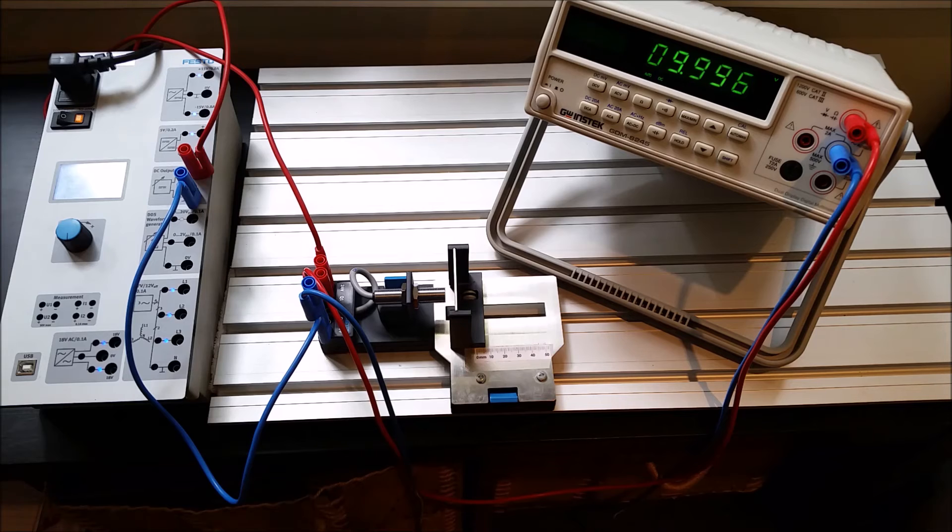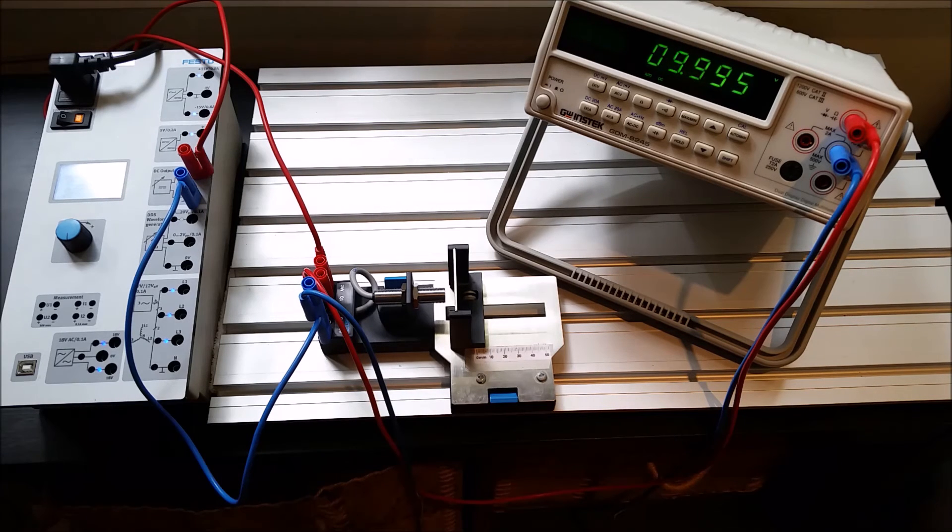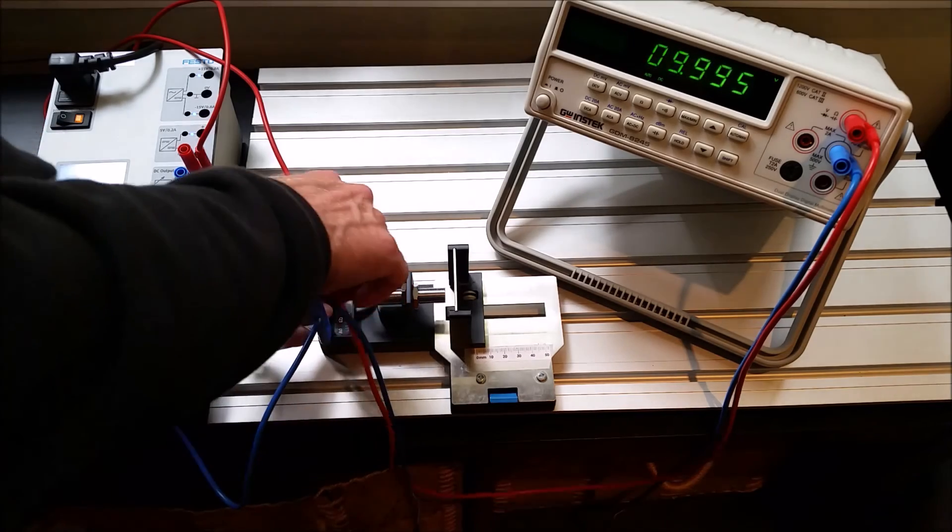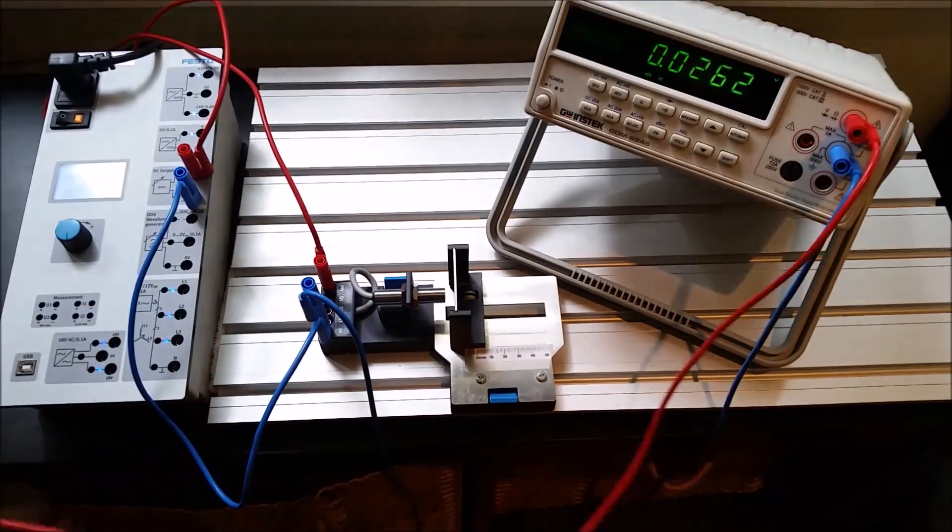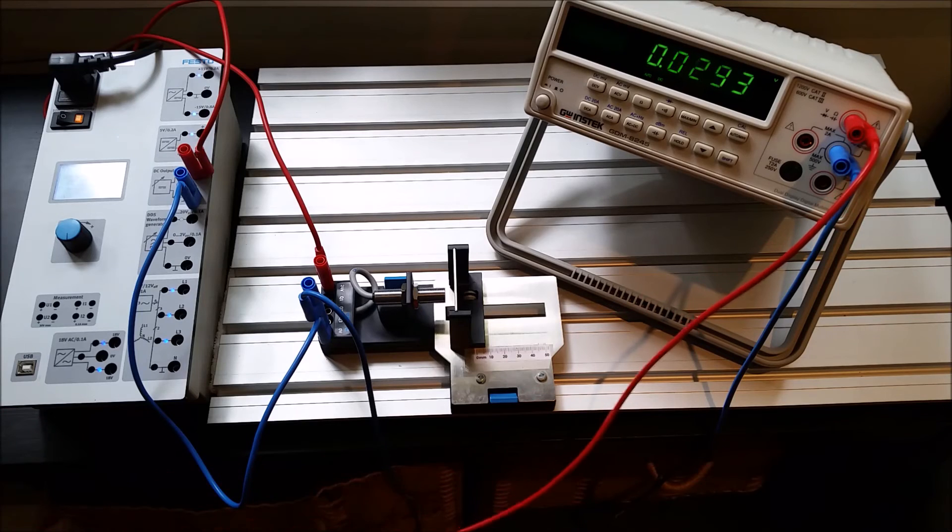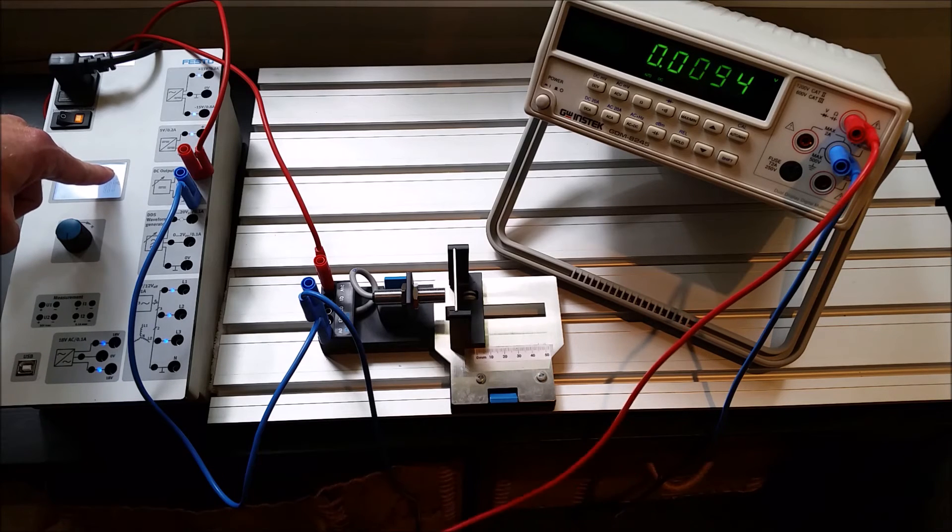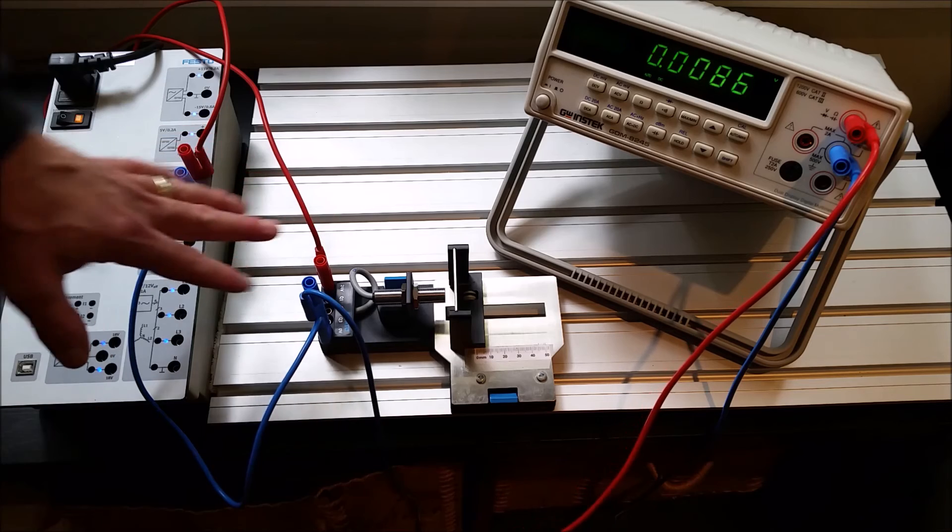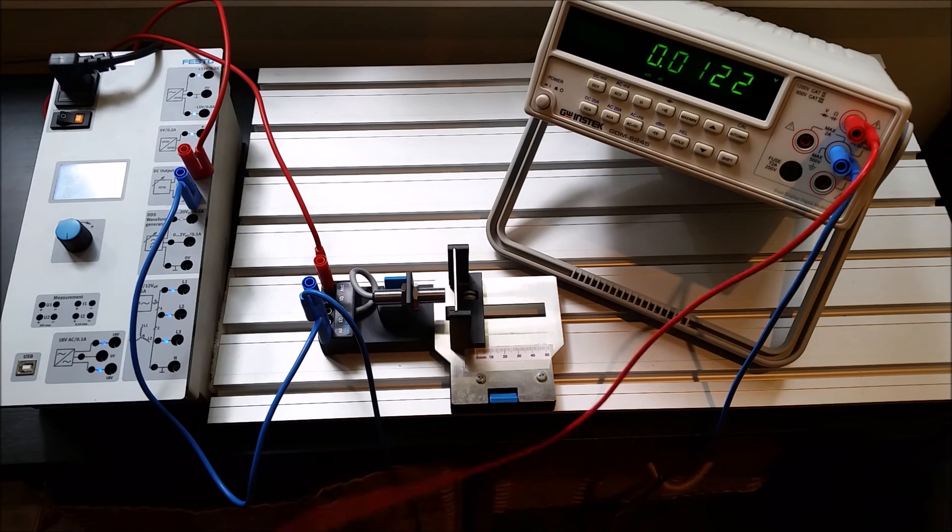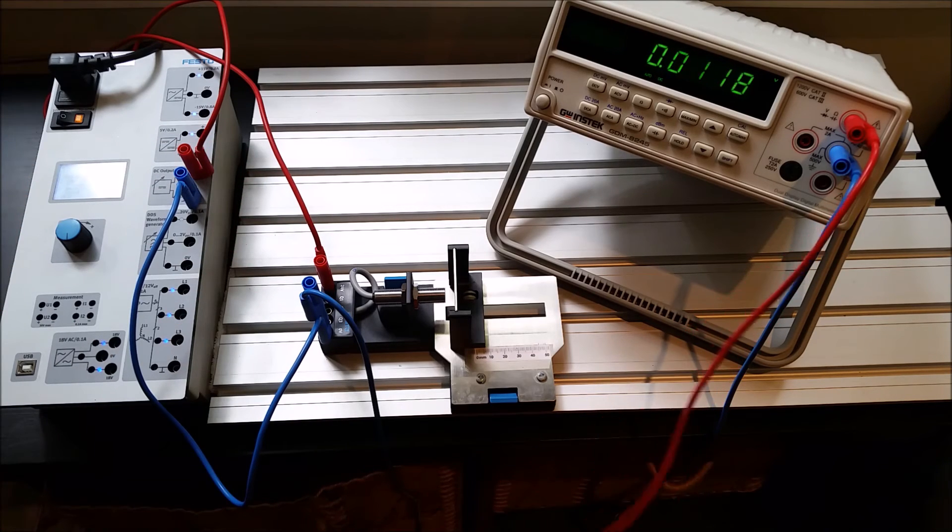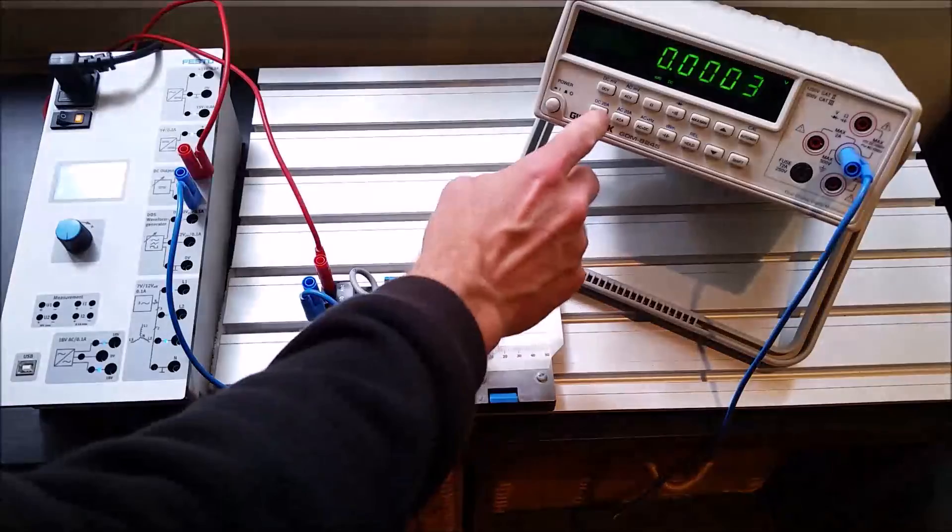So now we're going to switch it up and do current, because we've clearly seen the 0 to 10 volts DC. So what we'll do is we'll keep the power to the sensor here. With yours, yours is easy enough. Mine, I have to ramp up the voltage and everything, and I'm lazy. So I'm going to keep mine powered up. Please turn off your sensor as you're changing the different leads. Now that nothing is connected into my meter here, I'm now going to change over to DC current. So I've got DC current there, and it's going to make like auto range on its own.